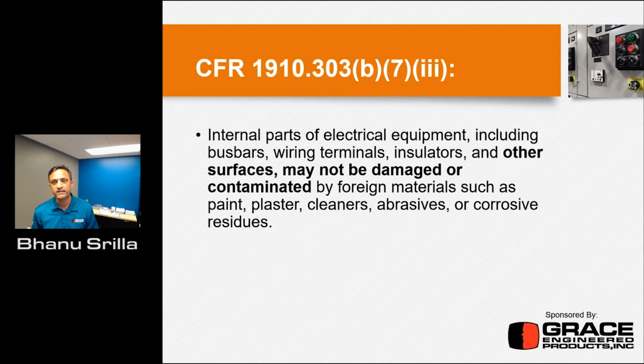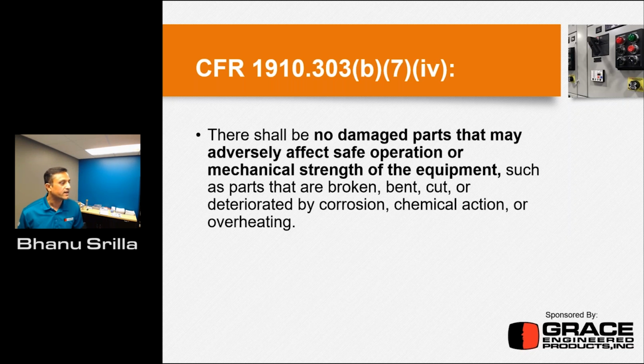So this is directly connecting to any type of loose connections within the bus bars or the circuit breakers or the bus ducts, whichever the electrical current carrying conductors. They need to make sure that these parts are maintained such that there is no contamination or damage to any of those. The next one is 1910.303. No damaged parts that may adversely affect the safe operation or mechanical strength of the equipment, right? So you can't have equipment running if there is structural damage to the mechanical strength or integrity of the equipment itself, okay?